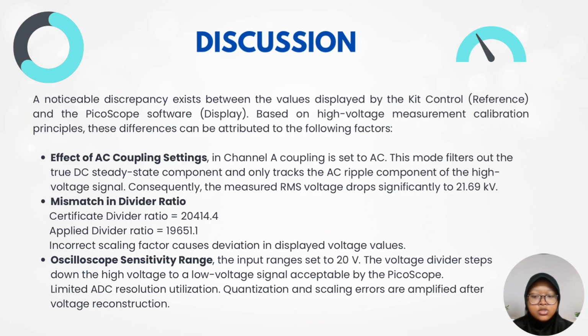In conclusion, accurate high voltage calibration requires DC coupling mode, the correct certified divider ratio of 20414.4, and an appropriate oscilloscope sensitivity range. These settings help minimize uncertainty and ensure reliable measurement results.